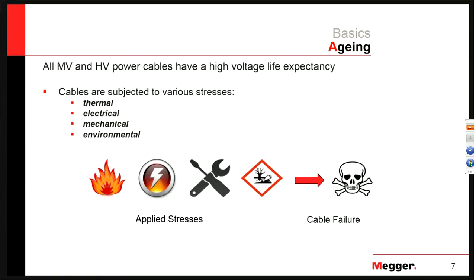Thermal stress can come from overloading the cable, pushing too much current through it. Electrical stress can come from over-voltaging the cable or regions of high voltage stress. Mechanical stress can come from nicks and scratches in the jacket during installation, or from over-bending the cable — when the cable is returned to straight, sometimes you get air bubbles and the layers delaminate, creating a cable failure. Environmental stress typically involves wet conditions that contribute to reduced cable life.